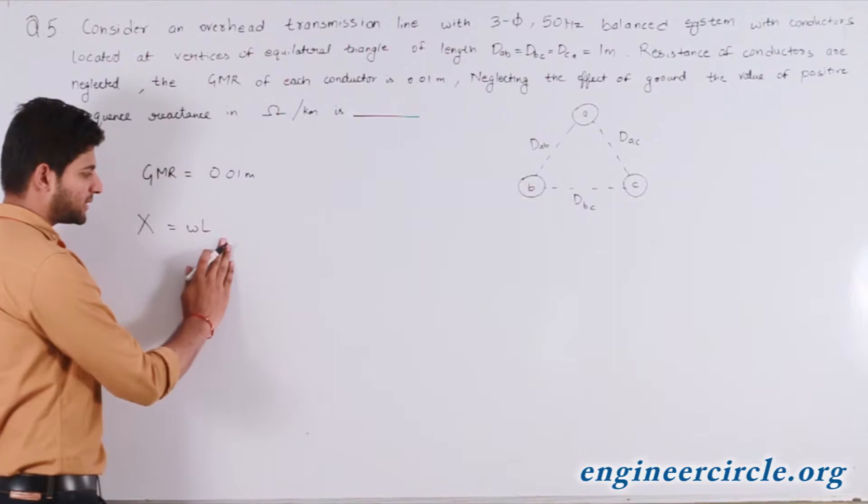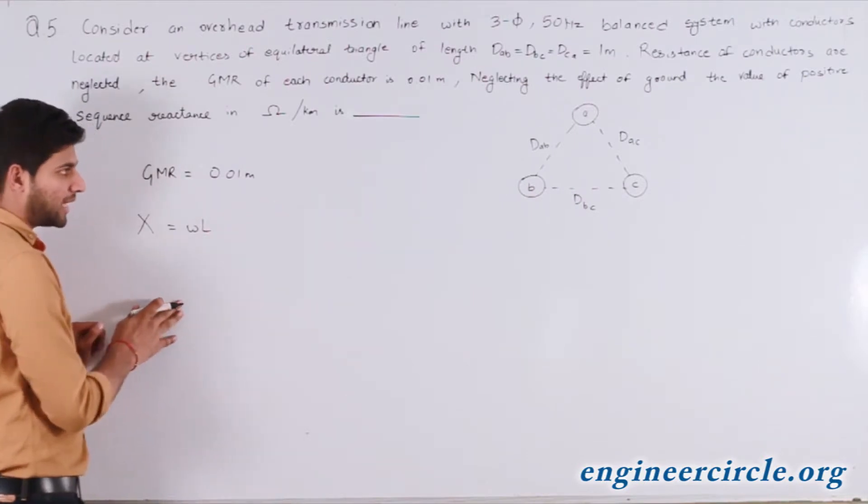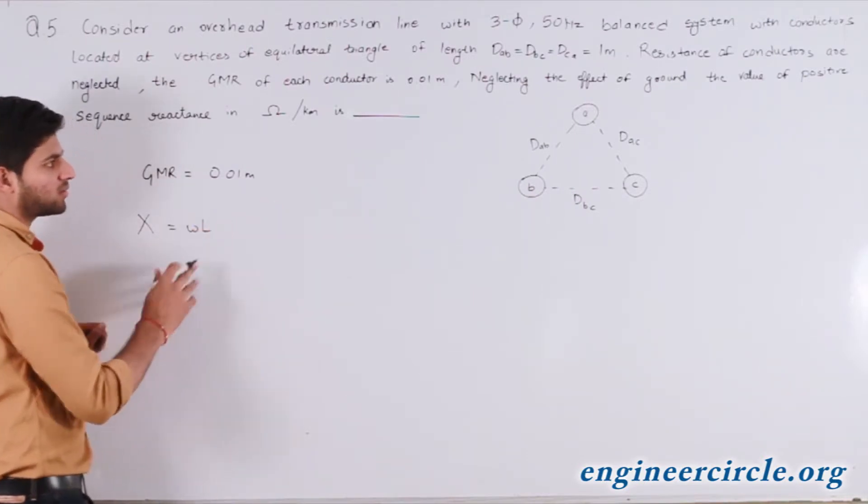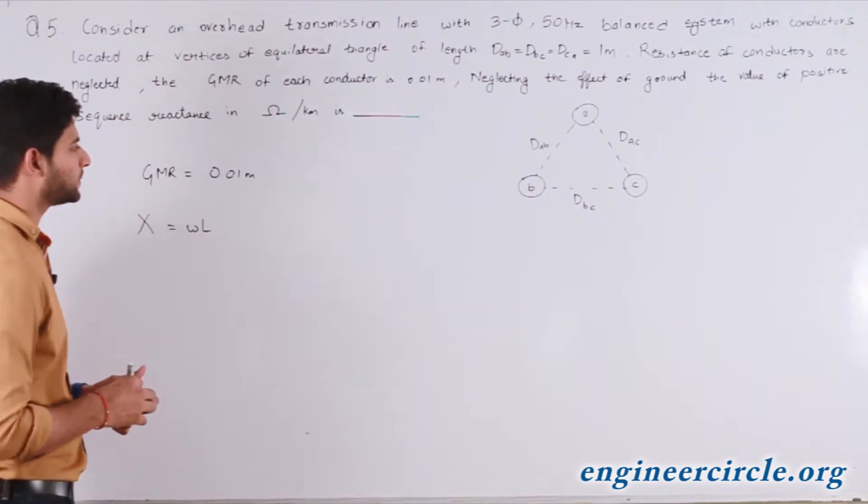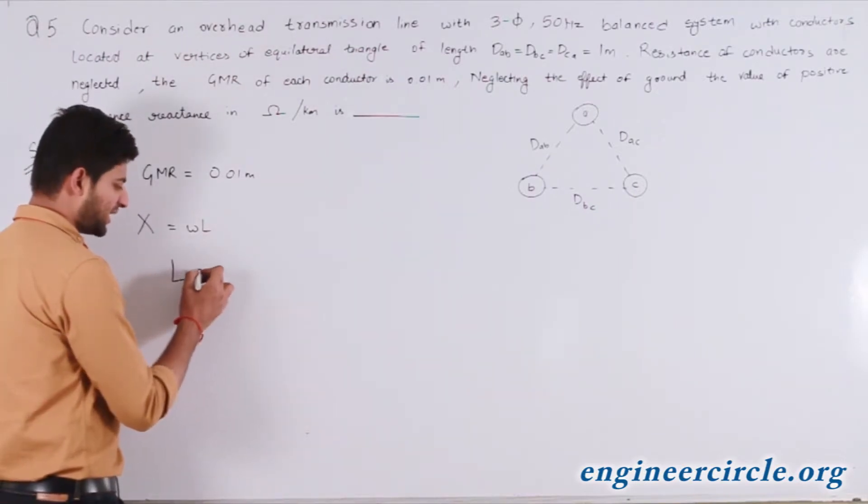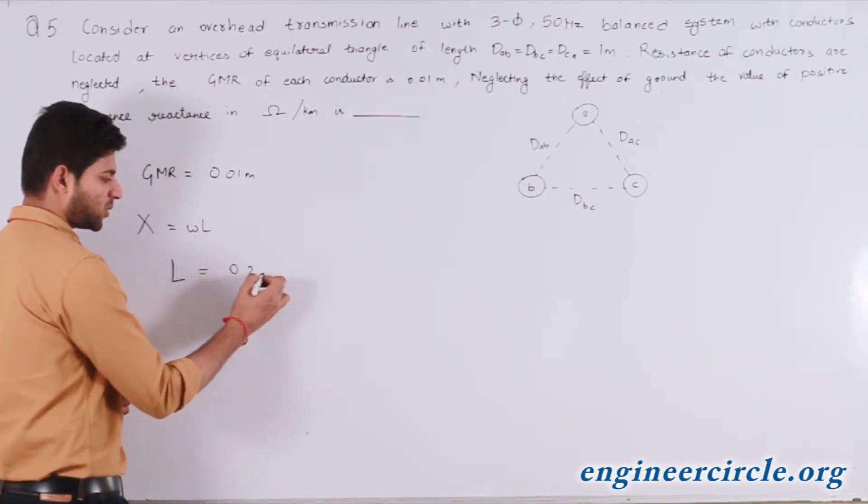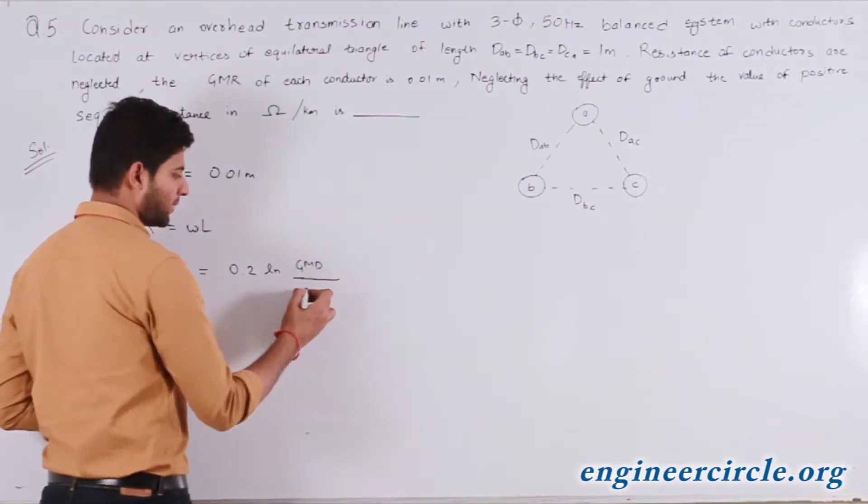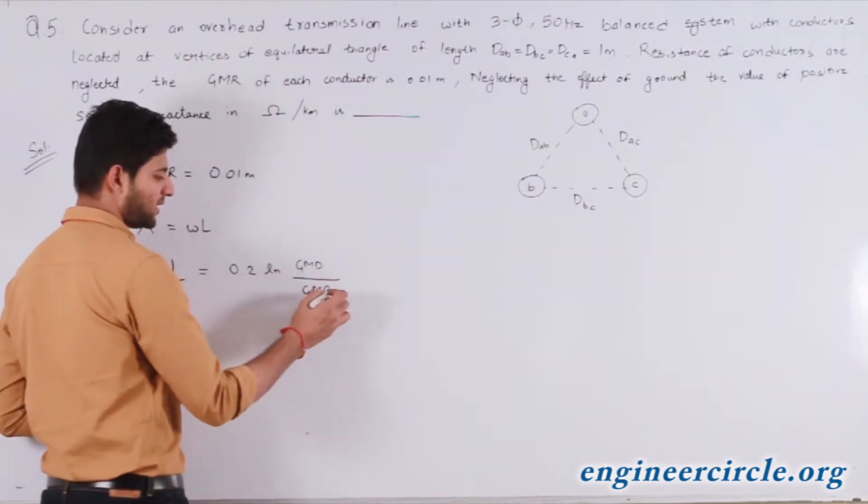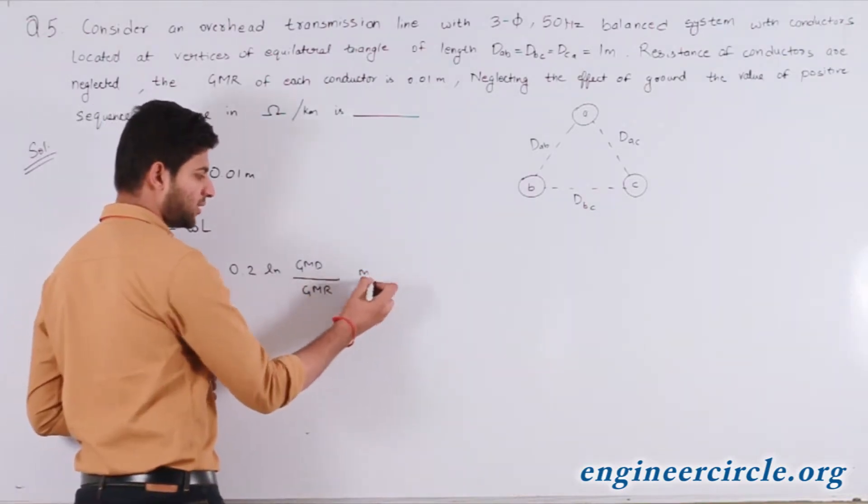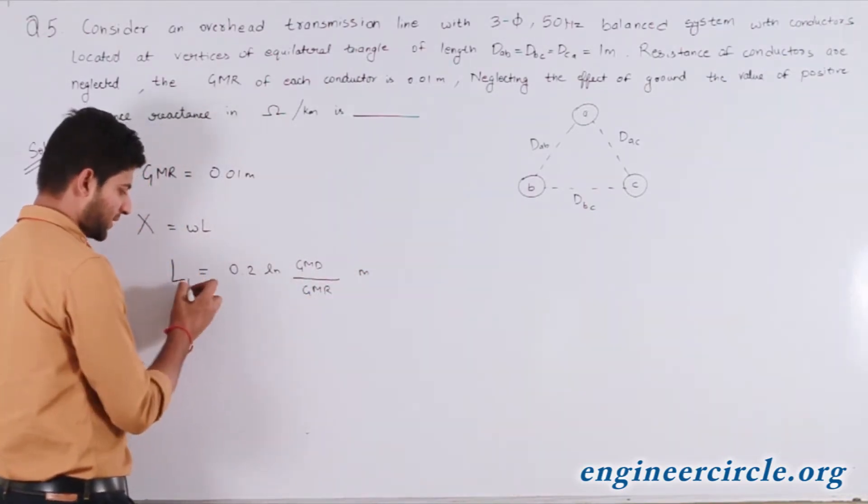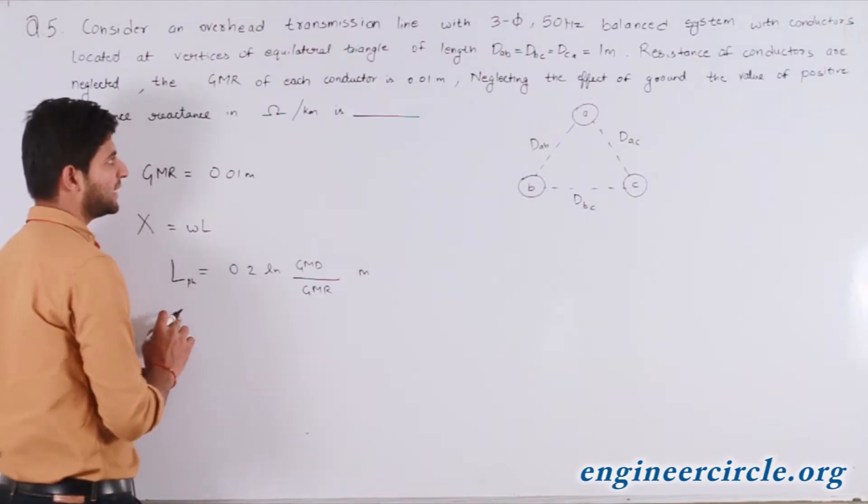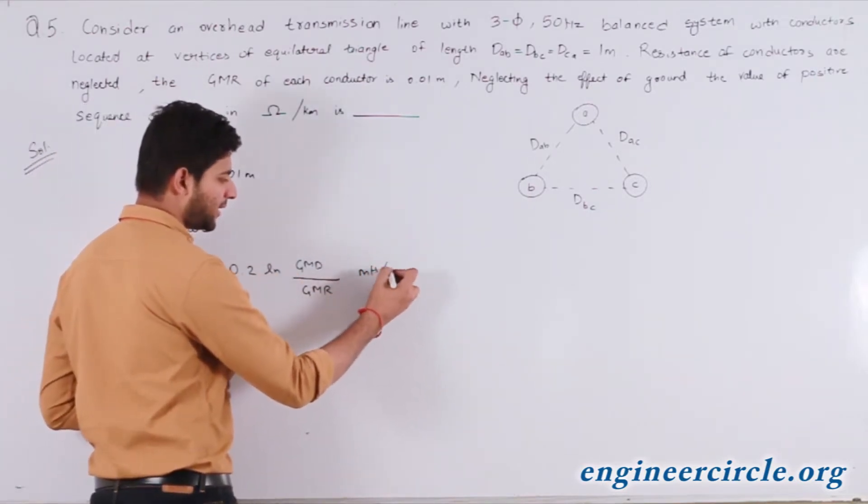The per phase inductance of this arrangement of bundled conductors or system of conductors can be found easily by L = 0.2 ln(GMD/GMR). This is the value of inductance per phase, calculated per phase in millihenry per kilometer.